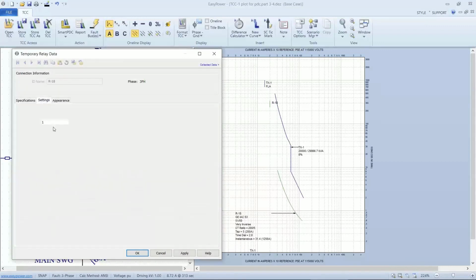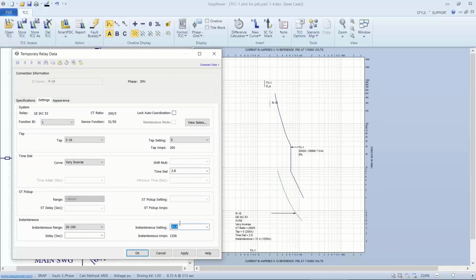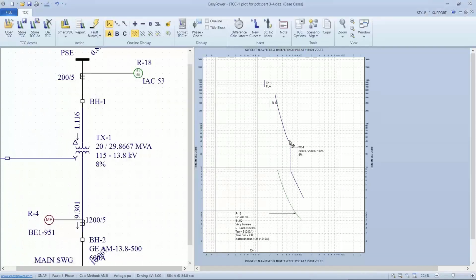We go back to settings, instantaneous. So we can adjust that with a little bit more granularity if we want. If we just set it for 31 on the dial setting, it gives us 1240. Let's call that good. And so we see that we have pretty good coordination, pretty good protection here for the transformer. Now, I said we could set this as high as 400%, which would give us 800 amps. If we left click and drag that tick mark up to 480 amps, we can see we're already exceeding the frequent fault curve. So it doesn't make sense to take the maximum setting allowed. We're trying to do this on a conservative basis. So I'm going to leave this at a pickup of 240, which gives me plenty of margin.